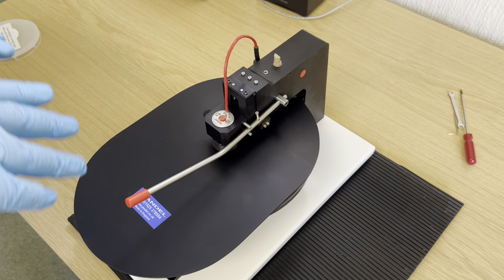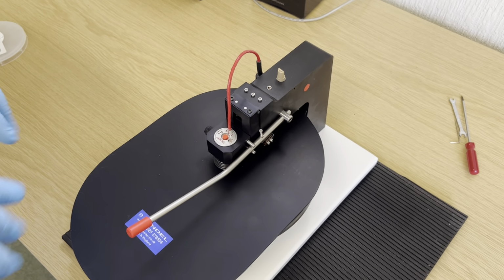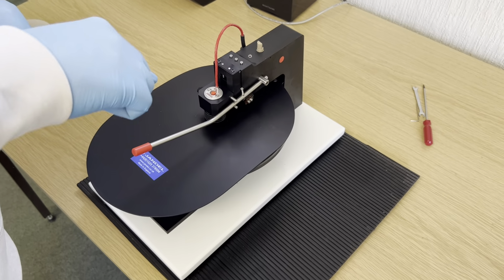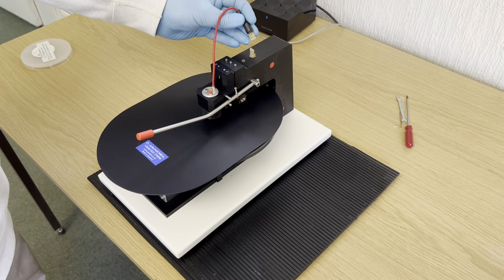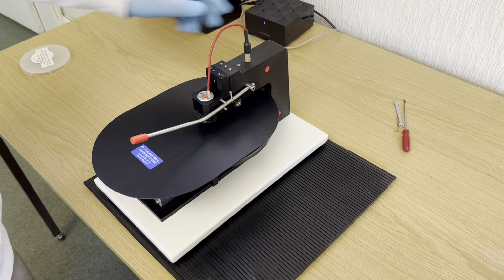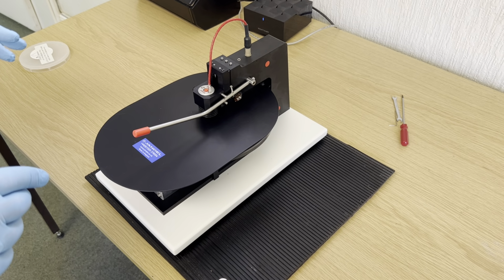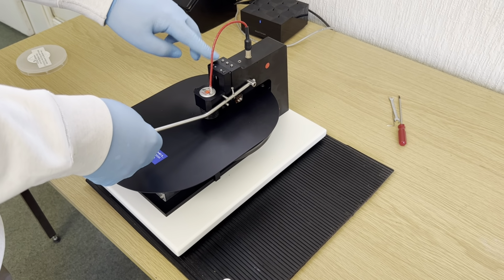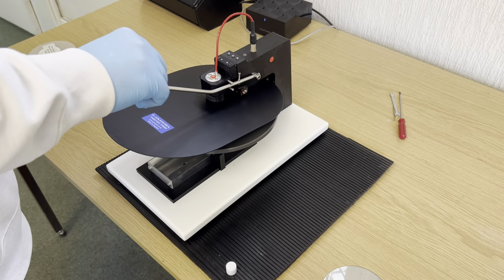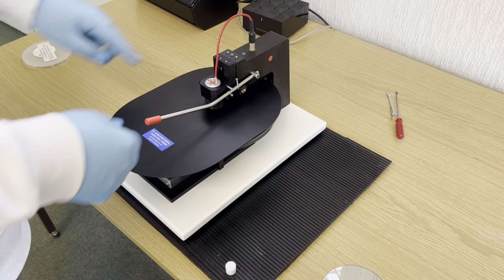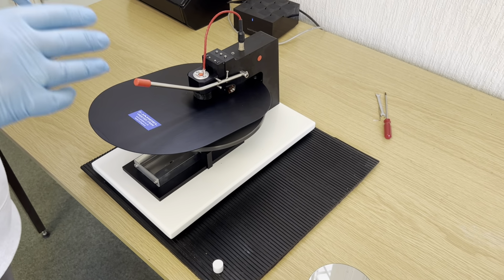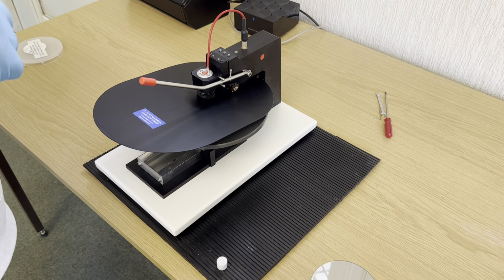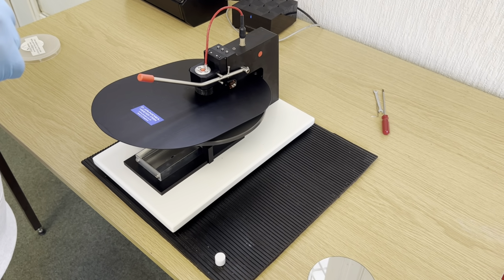This means that the probe head needles are now firmly compressed on the sample with the probe in its lowest position. Connect the probe head and we're now ready to make a measurement. The probe can now be raised and lowered onto the sample and will be at the correct height for all samples that are the same thickness.